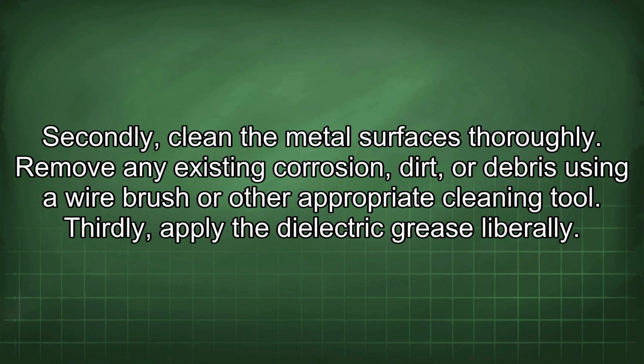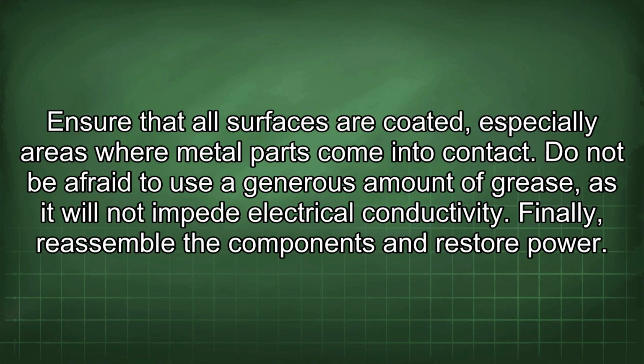Thirdly, apply the dielectric grease liberally. Ensure that all surfaces are coated, especially areas where metal parts come into contact. Do not be afraid to use a generous amount of grease, as it will not impede electrical conductivity. Finally, reassemble the components and restore power.